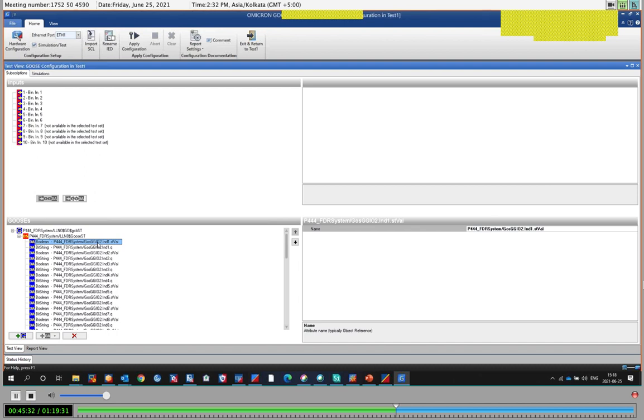I configured it in such a way. Again, this is a very poor kind of configuration. The better way would be to use the correct naming, such as PTRC. So now I can just connect it to binary input one, like this. And now, if this bit in the GOOSE goes from 0 to 1, it will make my binary input 1 go low to high. And then this low to high will trigger the timer, and I can record the trip time. So the first data attribute in this GOOSE, a tripping signal, has been received by the first binary input of my test set. And this is how we map it.